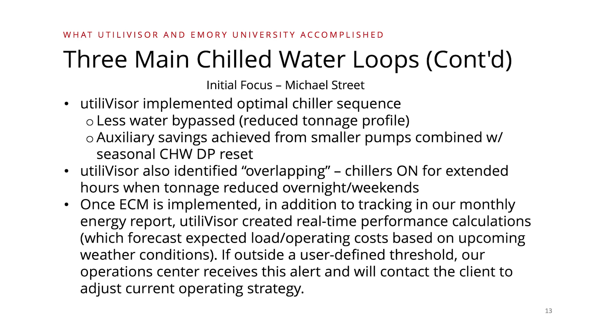But what we noticed is that the load was a lot higher at colder temperatures. The reason is that they were bypassing so much more water, because basically they had too much muscle. So if I was an engineer looking at the BMS, I would be misled, because I would think overall efficiency is beating the standard and that I'm good. But what we found out was, even though you operated a smaller machine that was a little less efficient, in the grand scheme of things, because you were producing less tonnage, you had less kW overall, and your cost was a lot less.